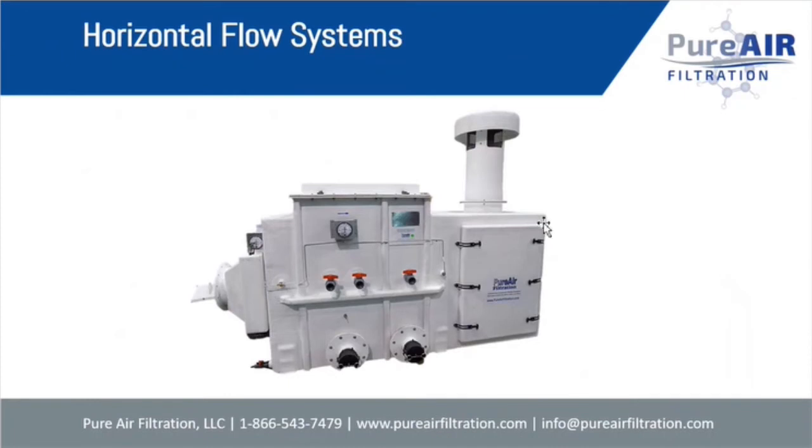We have fiberglass systems. This is a specialty system, a horizontal flow system with two individual beds here. Let me back up. First, there's an integrated mist and grease filter. And then there's one adsorbent bed here that's 2 feet deep, and another adsorbent bed here that's 1 foot deep. So we can use two types of adsorbents and independently change them if we have to. And here is a fan section, an enclosed, super quiet fan. So it makes a really nice quiet system.